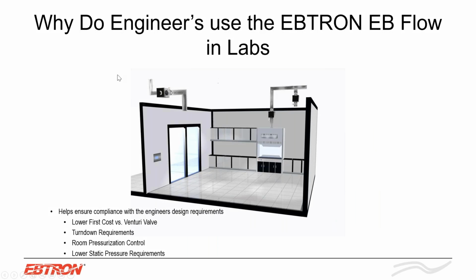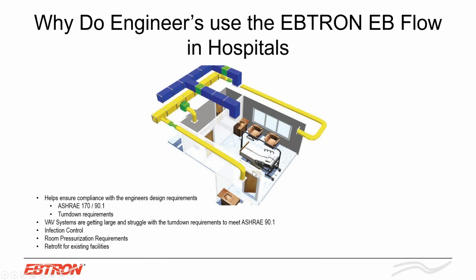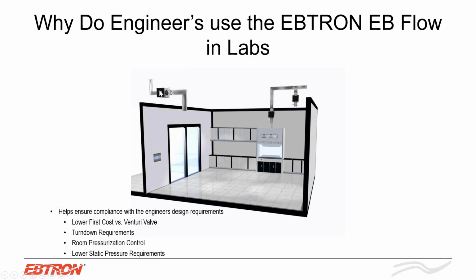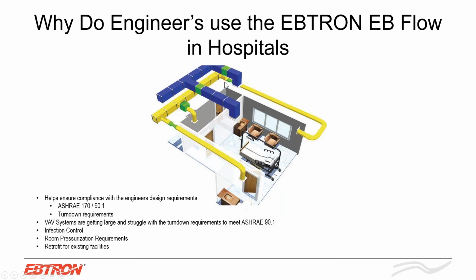Again, I talked about labs, lower first cost versus Venturi valve. Again, we are kind of the VE situation for lab type applications. And both for labs and for hospitals, you know, it's room pressurization control. It's installing these units on the supply and any return, and if there is exhaust, to maintain that pressurization if it's an isolation room, if it's an OR room, depending on whatever type of application you were designing.